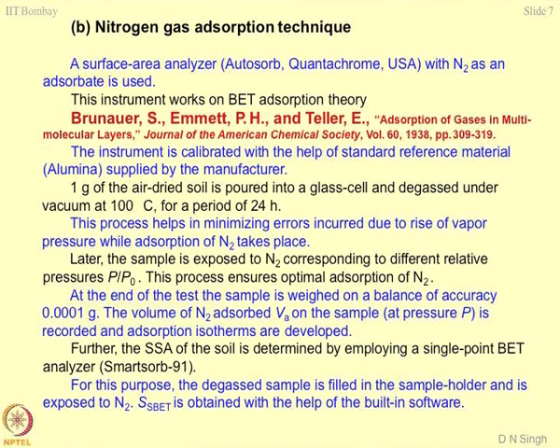Most of us were not even born when this method was developed. This instrument has to be calibrated first with the help of a standard reference material — normally alumina, which is supplied by the manufacturers. One gram of air-dried soil is poured in a glass cell and degassed under vacuum.